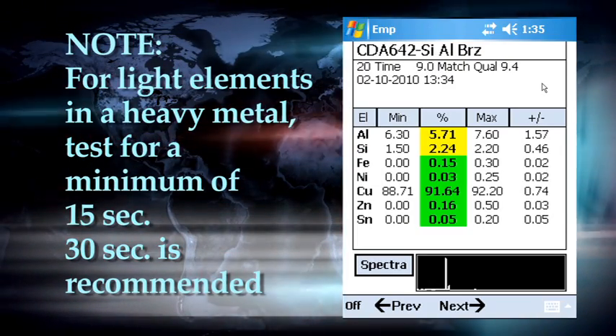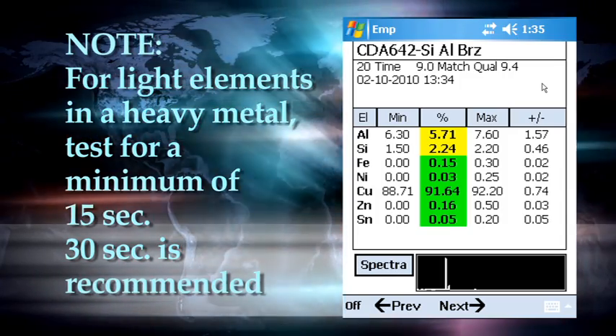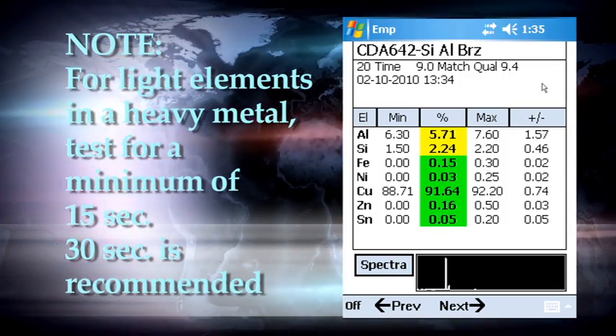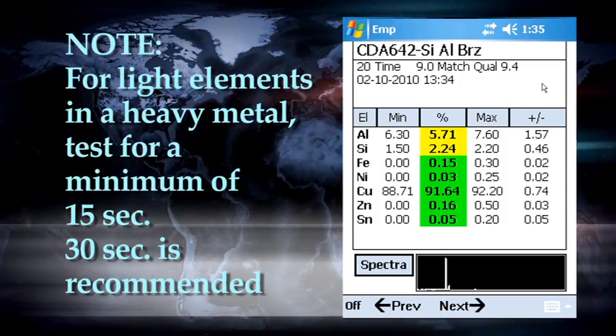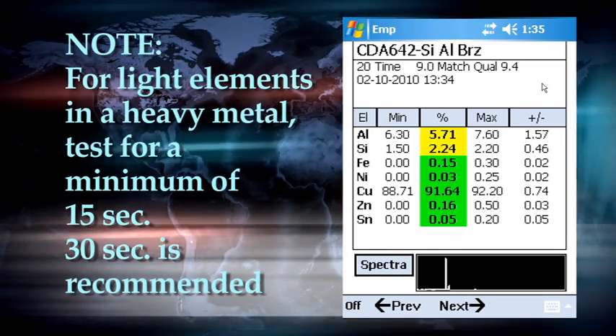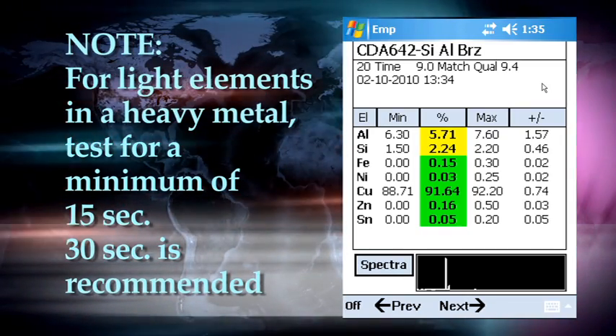In order to measure light elements in a heavy metal matrix, like steel or copper, a minimum measurement time of 15 seconds is required. 30 seconds will provide an accurate analysis of the light elements.